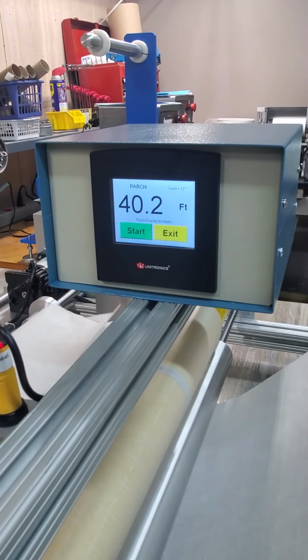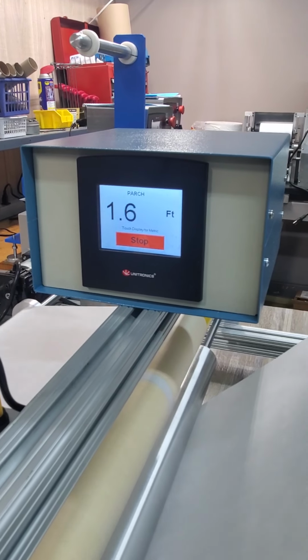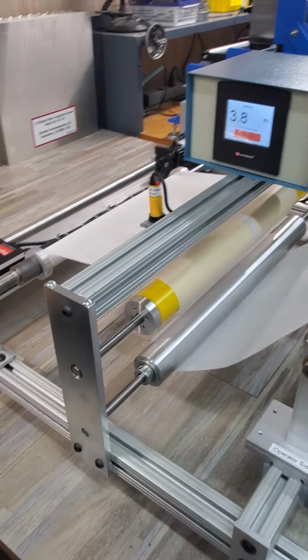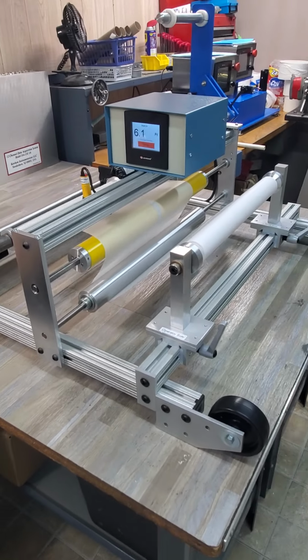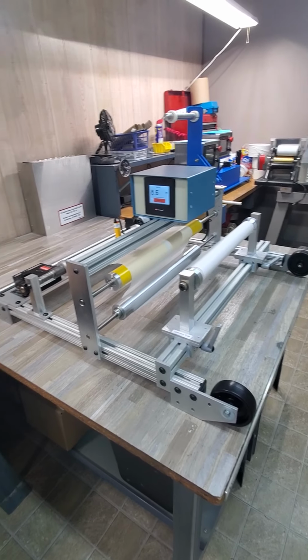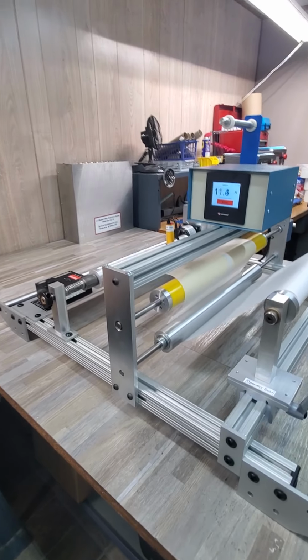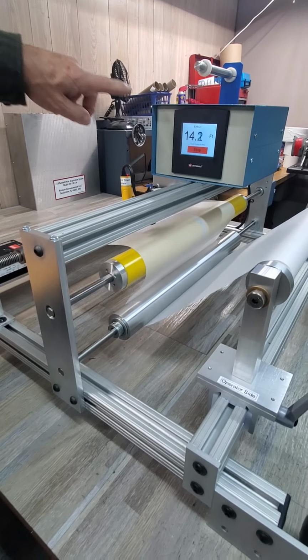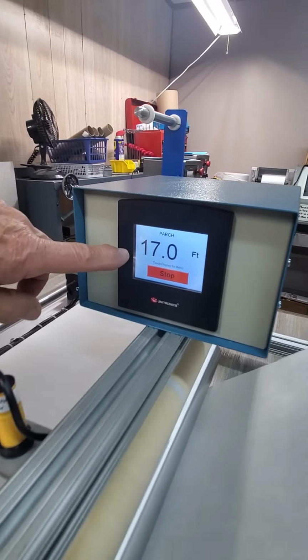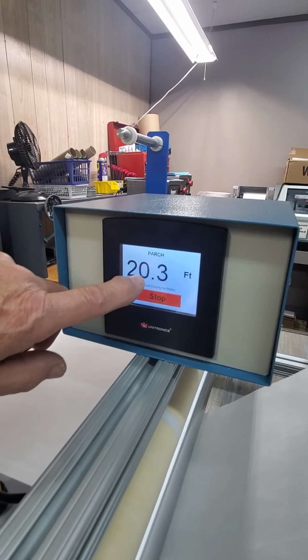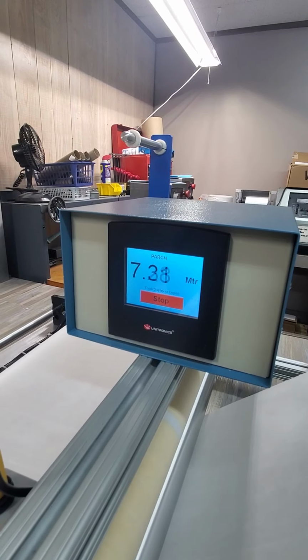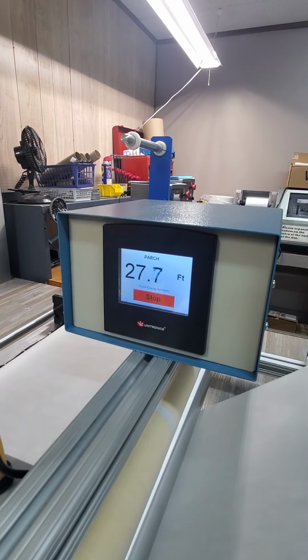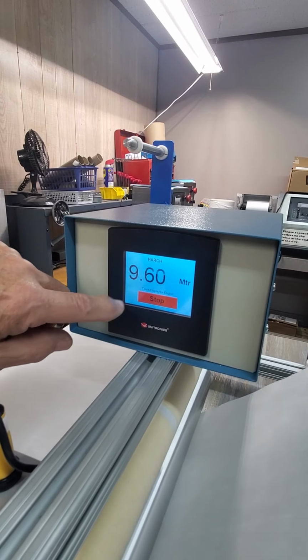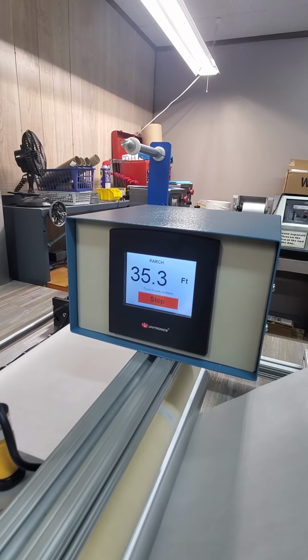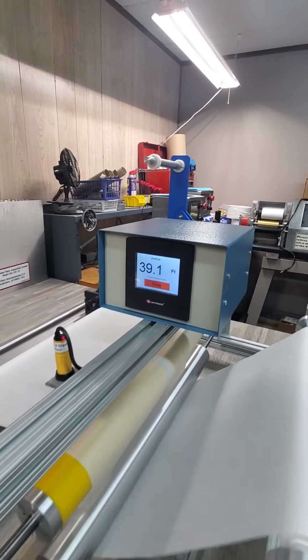All right, so we're going to go ahead and start the test. Now to start the test, I simply push the start button. The motor is rotating the wind-up shaft and feeding the material through the machine. If you look up at our counter, you can see it's counting up. Now if I want to display this in metric, I simply touch the display. It will toggle to meters or to feet. So we'll go ahead and let this test finish.